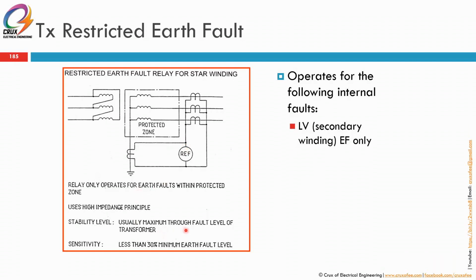So usually maximum, the stability level is usually maximum through fault level of the transformer. Sensitivity normally is set to less than 30% minimum of fault level lah. So it only works when there's a fault within this CTs lah, which is this zone lah. This is a protected zone lah. So normally these three CTs are located at the switchgear, so it will also cover not only the transformer secondary winding as well as the cable lah, or bus bar or bus duct if it's used. So LV secondary winding, earth fault only.